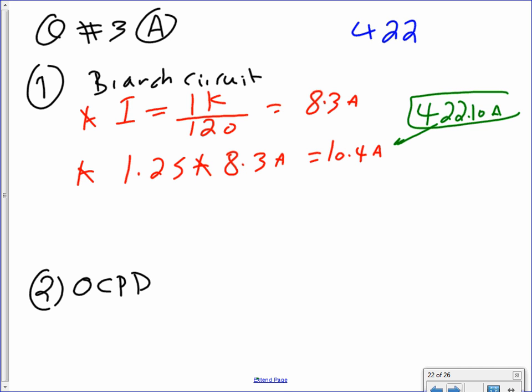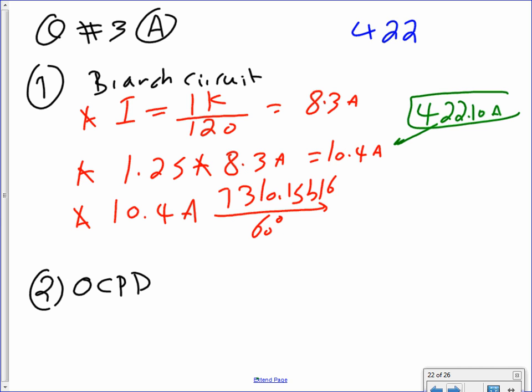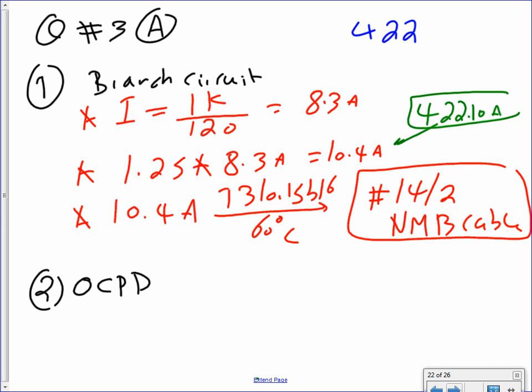Then you take the 10.4 amps. You're going to take it to table 310.15 B16, 60-degree column. That will get you number 14 AWG in an NM cable. So for this load, you need number 14.